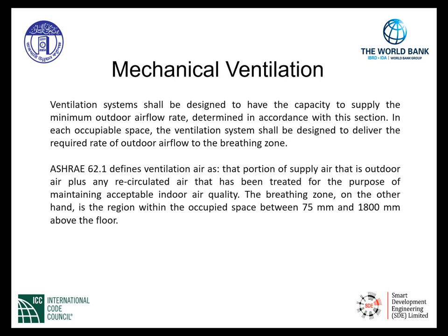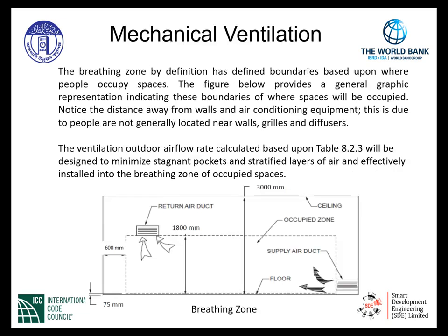The breathing zone, on the other hand, is the region within the occupied space between 75 millimeters and 1800 millimeters above the floor. The breathing zone, by definition, has specific defined boundaries based upon where people occupy spaces.